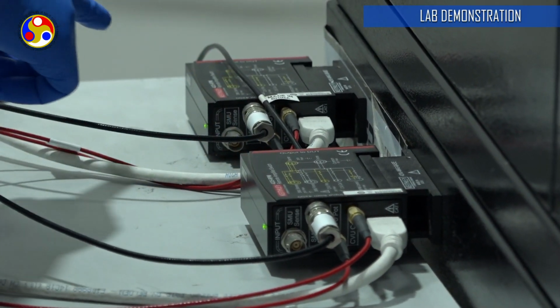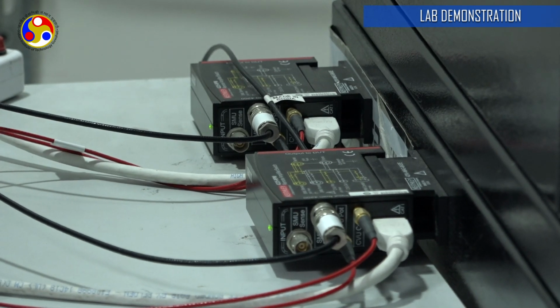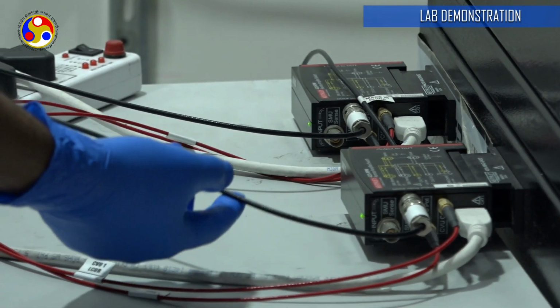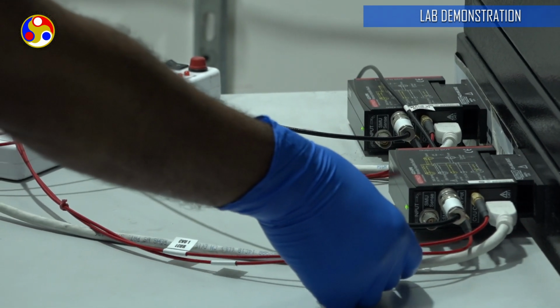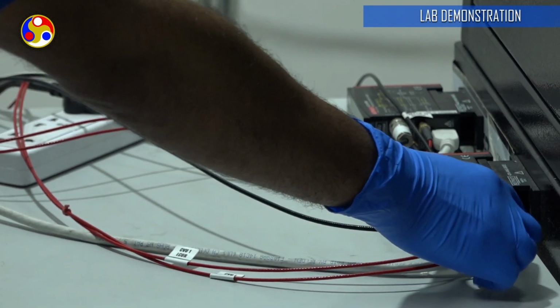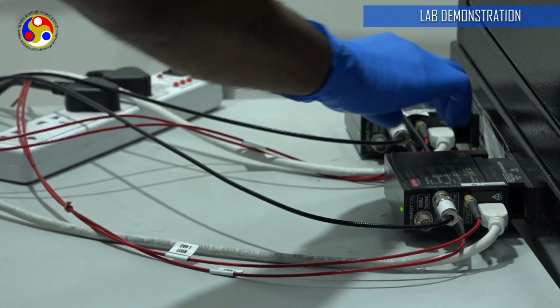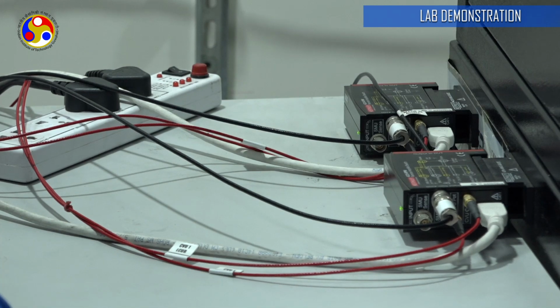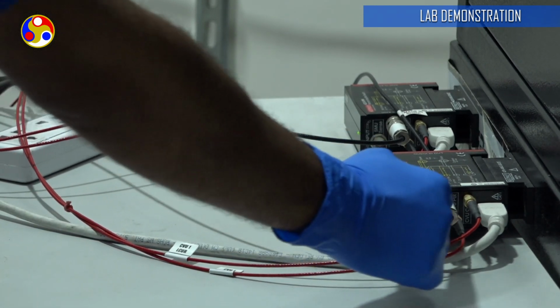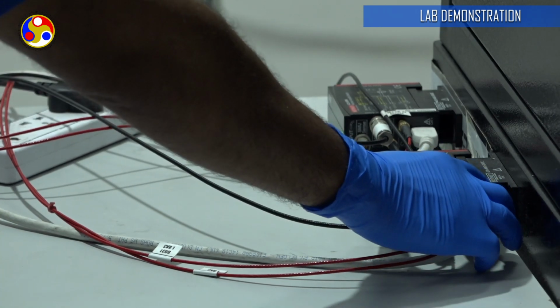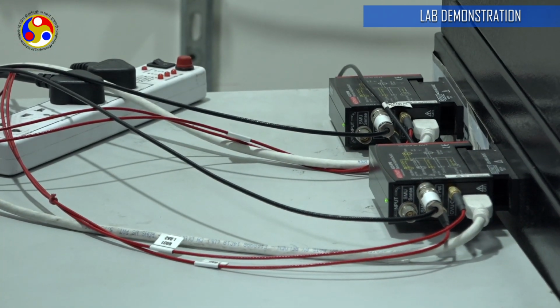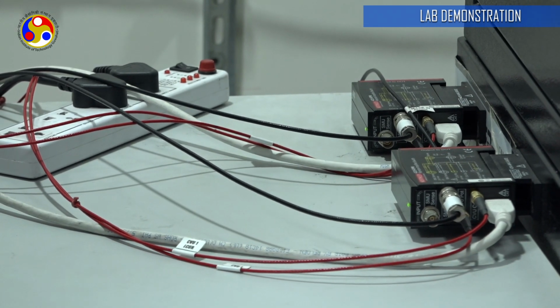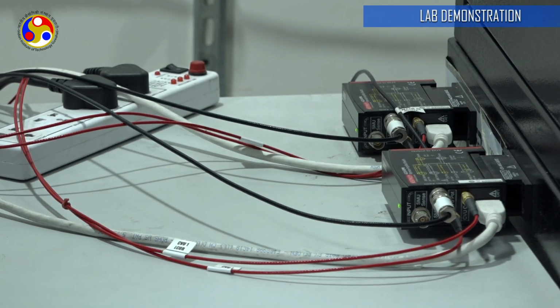And these two units are basically multiplexers and amplifiers. So the signals from SMU 1, then the capacitance voltage and pulse measurement units are going into this multiplexer, and one output is coming out. So depending upon our test, the input is chosen between these three. So this is a multiplexer unit as well as an amplifier unit. It will amplify the low current and low signals to a desired level so that it can be read by the 4200 SCS machine.